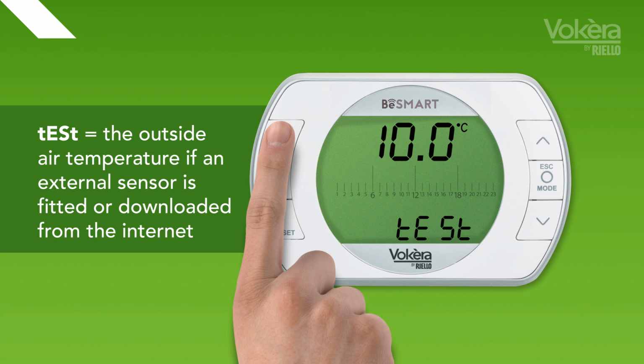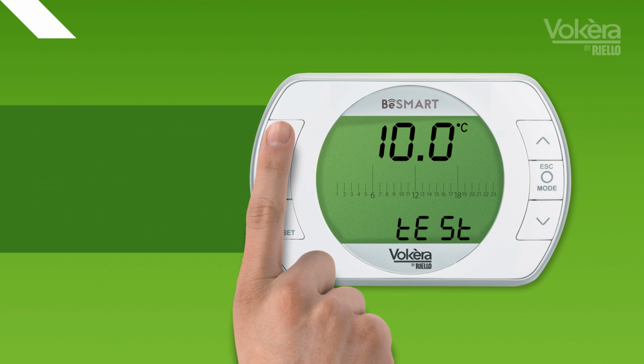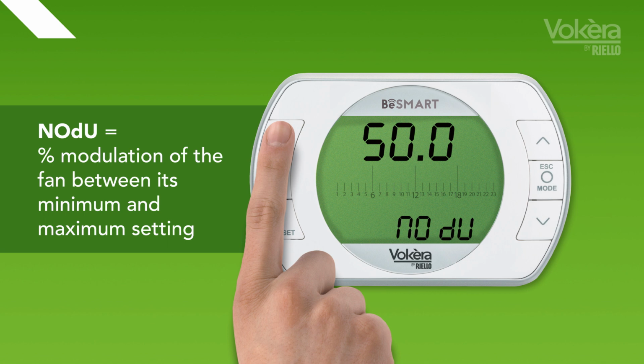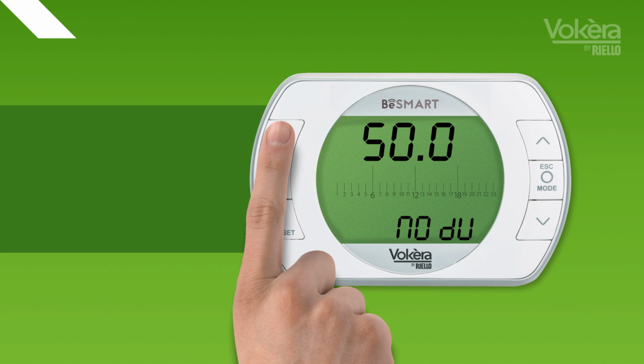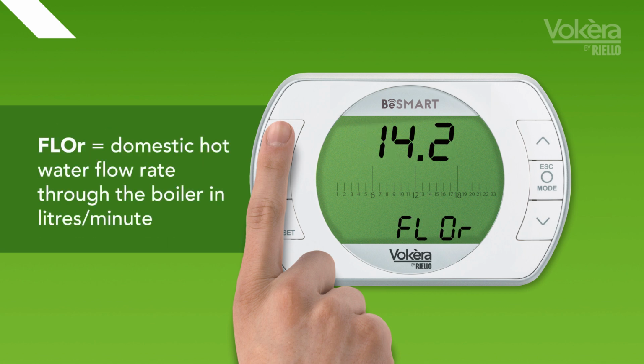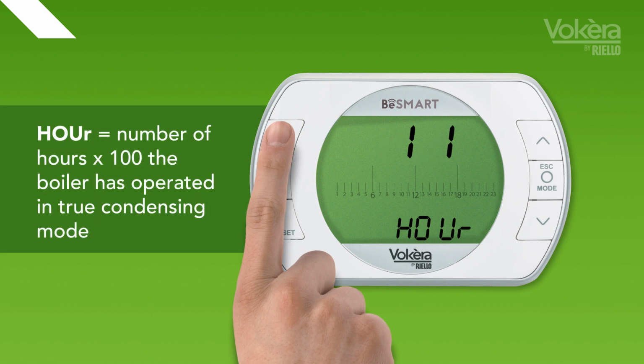tESt is the outside air temperature if an external sensor is fitted or if external weather conditions are downloaded from the internet. NODU is a percentage modulation of the fan between its minimum and maximum setting, an indication of the power output of the boiler. FLOR is the domestic hot water flow rate through the boiler in litres per minute. Hour equals the number of hours times 100 the boiler has operated in true condensing mode.